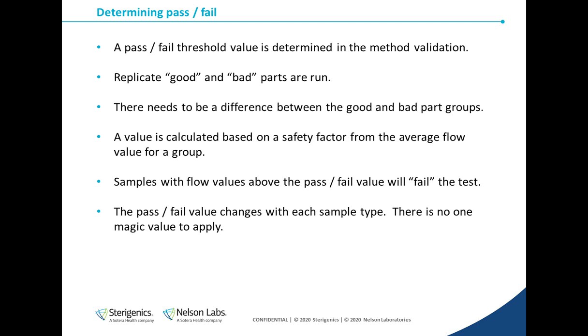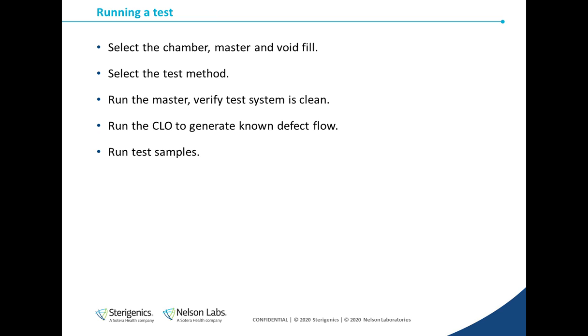Where is this pass-fail threshold coming from? There's no one number that's appropriate for all tests, so the value has to be determined through validation of the method with a certain sample type. A set of non-leaking or good parts are tested with the method, and those final flow values are determined. Then the samples are run again with the CLO on to simulate a defect of known size. These two sets, the good parts and the defective parts, are then statistically compared to one another, and a value somewhere between the sets is calculated as the pass-fail threshold.